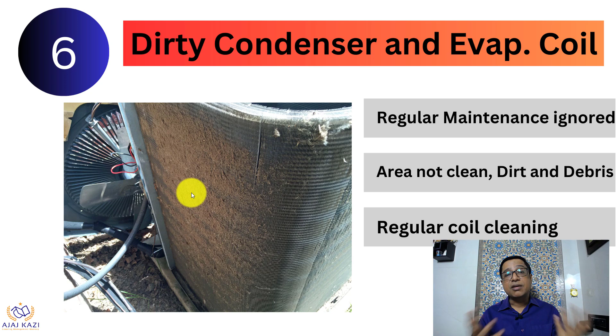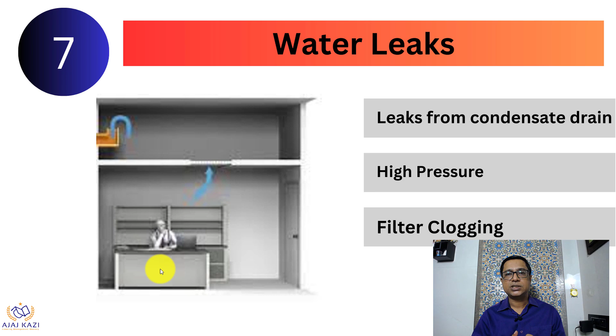The seventh issue or problem is water leaks. Leakage from the water pipes, if they are not tested properly, there is some flange leak or something else, a gasket is giving way, that leads to a leakage. The second leakage is the drain pipe. You will always find this is a major leakage. Drain pipe from the air handling unit. You can see a person over here sitting below the unit. The drain pipe leaks and it goes on top of his head. The leakage from the drain is also due to filter clogging. This is one of the important causes of leakages.